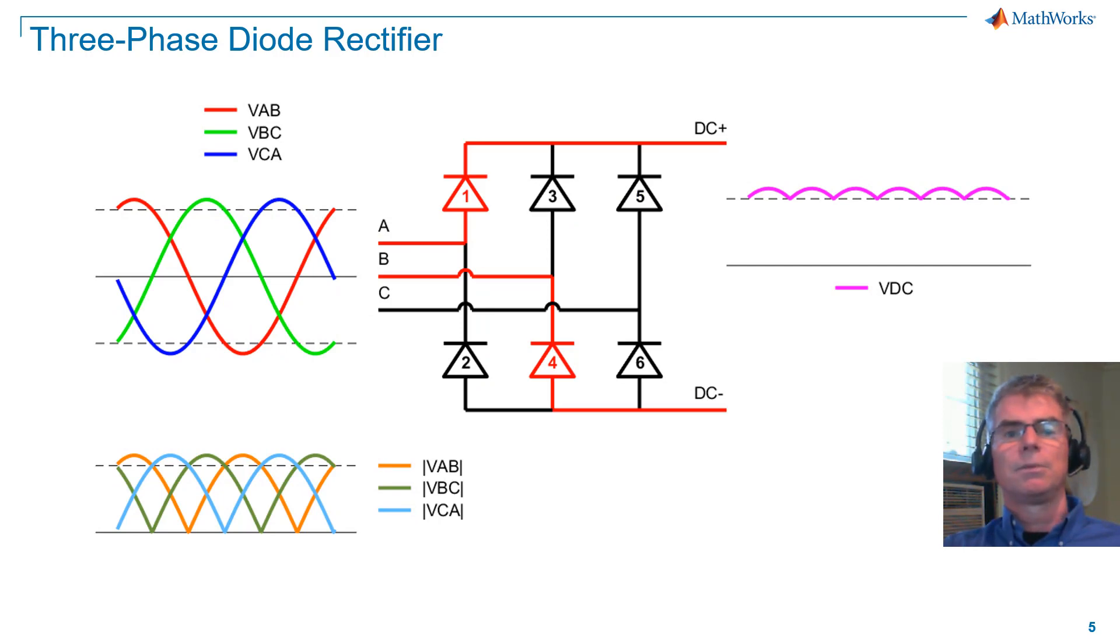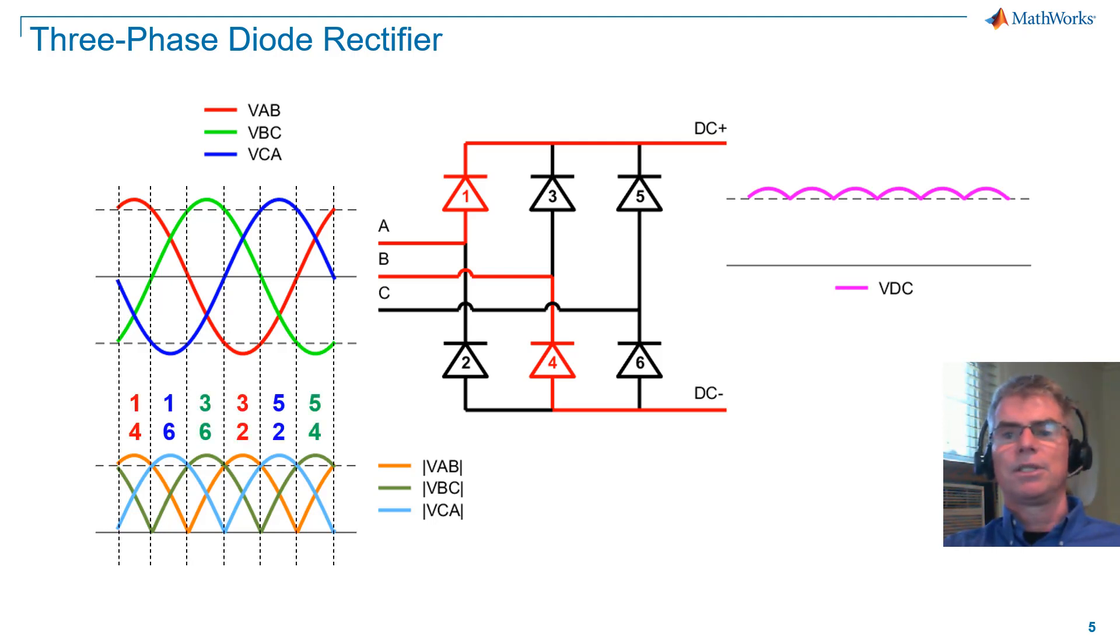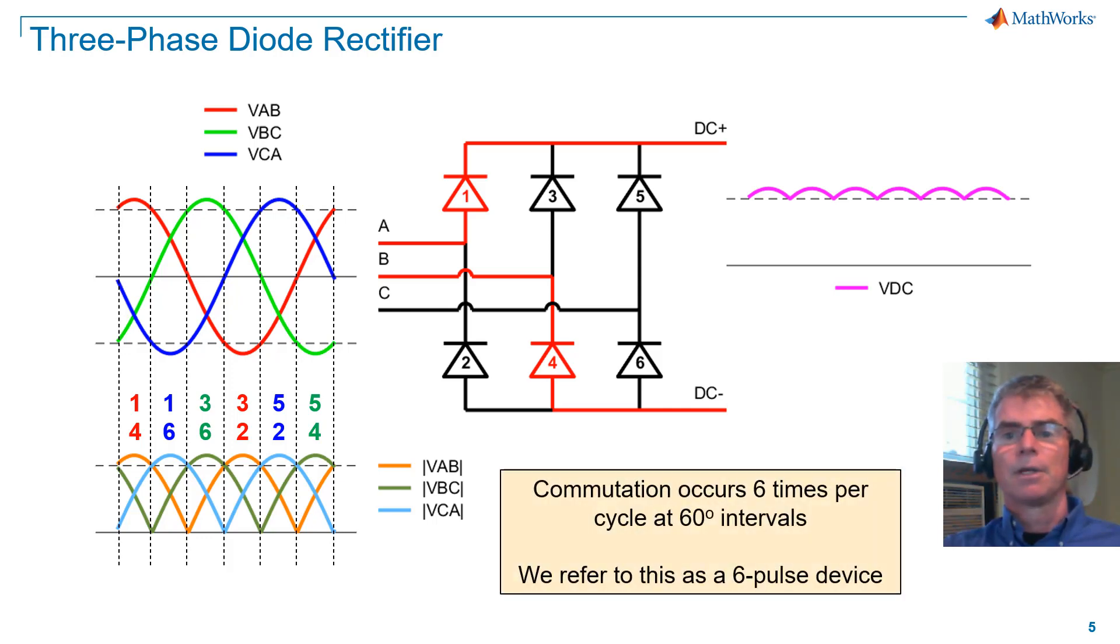If we look at the commutation sequence, you can see that there are six commutations in a single cycle, and so commutation is occurring every 60 degrees. As there are six commutations per cycle, we refer to this as a six-pulse device.